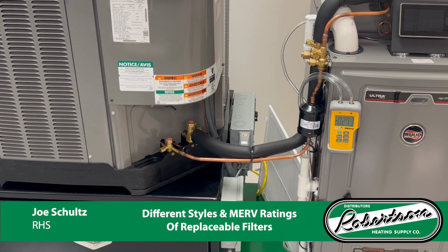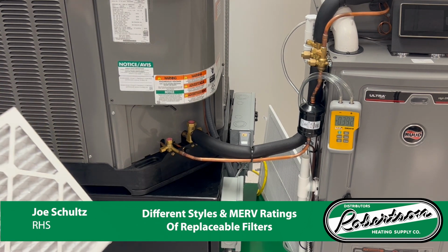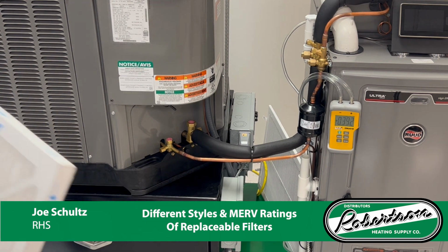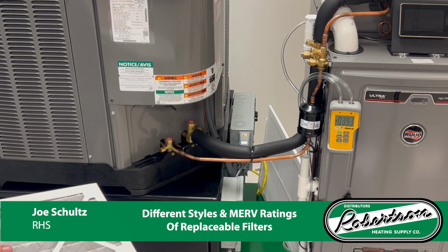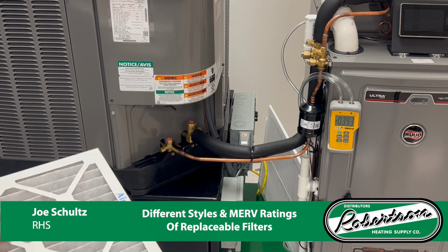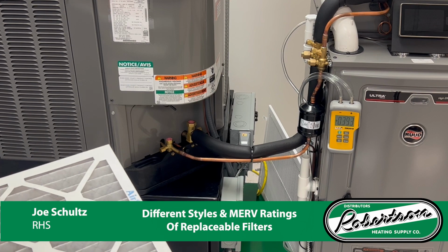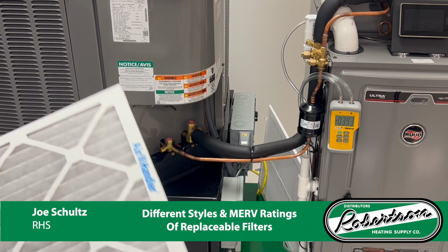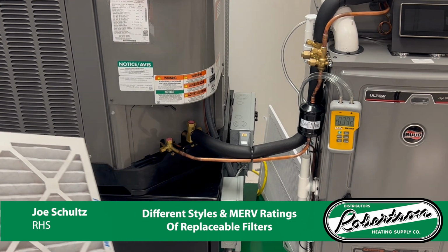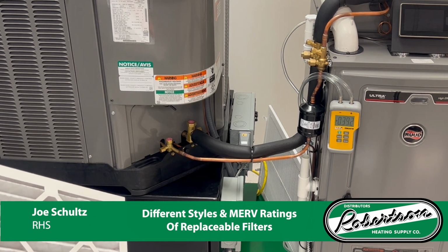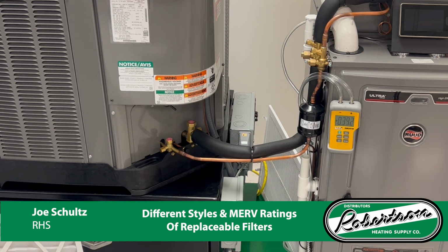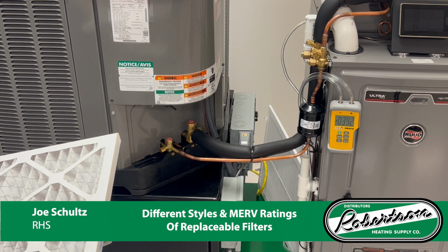The one thing that's important to point out on these filters is you really want to make sure that you put in the filter properly, because there is supporting mesh that holds this filter from unraveling, and then different pieces of cardboard that keeps that. Some filters don't have this supporting cardboard. If you put it in backwards, that filter will unravel, and then the customer will have a difficult time pulling it out in the future.